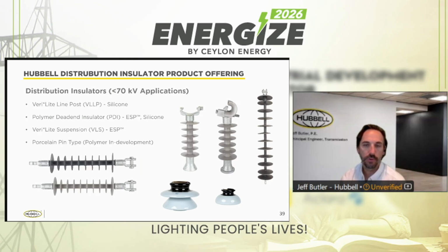That's what's shown on the far right. And those are direct glass bell equivalents. So those, we sell them in 3, 4, 5, and 6 bell equivalent sizes. So the idea being that you don't have to change your sag, you don't have to retension your line. You can directly replace glass bells with those insulators. And then we have porcelain pin types, as well as we are in development of polymer pin types. And that polymer is not silicone rubber or EPDM, but that's an HDPE or high density polyethylene material.